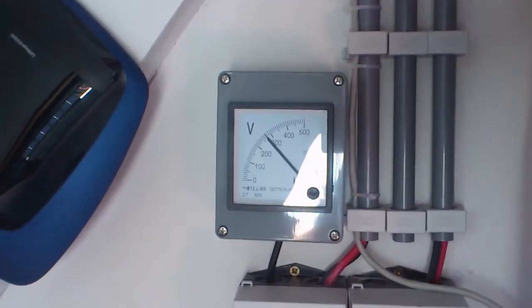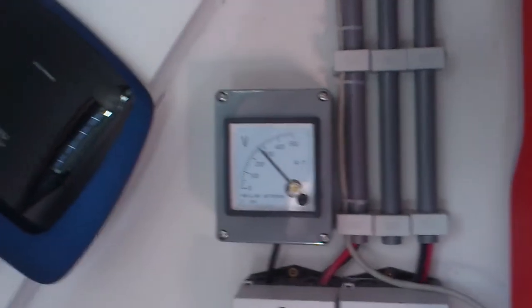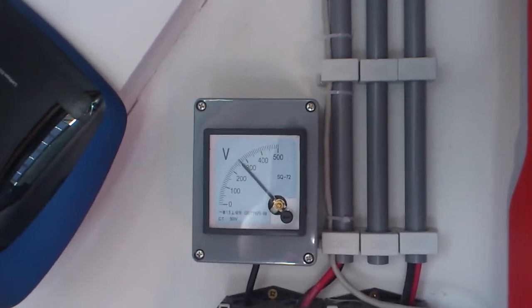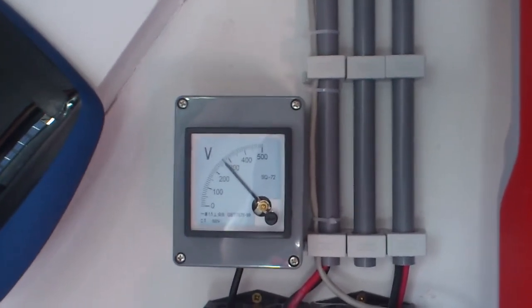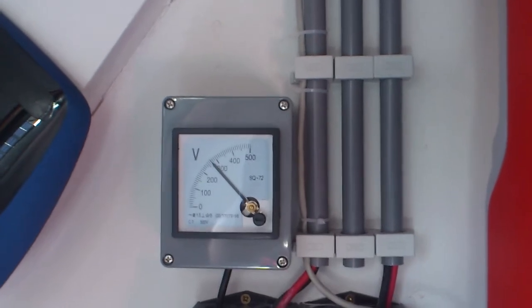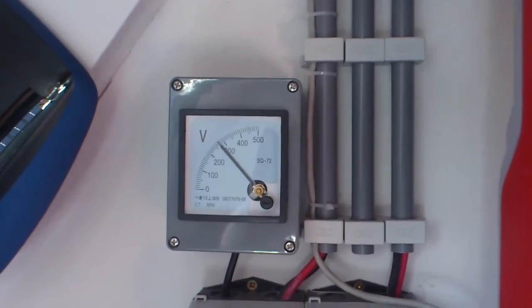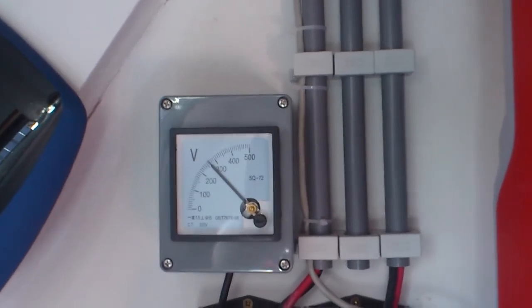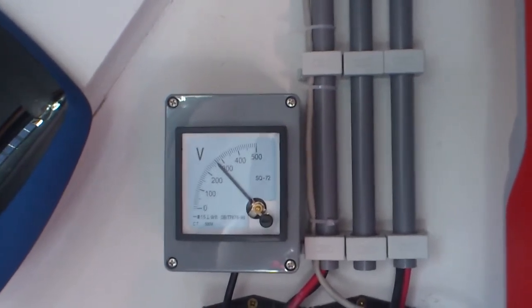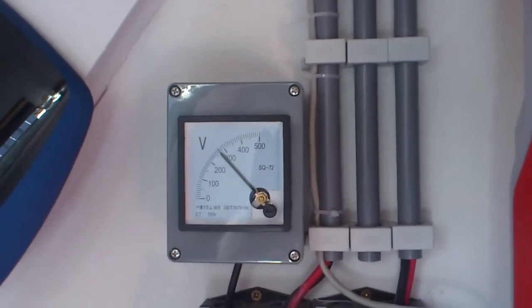And that means it goes all over the place, which is very nicely visible on the voltage meter. What I was hoping to capture is the MPP sweep of the OptiTrack from the SMA HF series, which I wanted to illustrate with the analog meter, which is far better visible than a digital display ever could. So what you will see when it does perform the MPP sweep is that the voltage dial moves rapidly between 175 and open voltage of the string, which is about 320, trying to find the best spot.